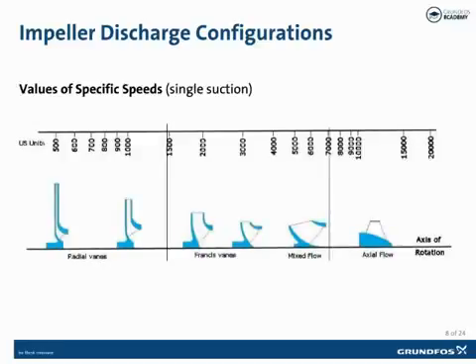Specific speed is a dimensionless value. This chart shows the relationship of specific speed with impeller types. Specific speed is defined as the speed at which a given impeller would operate if reduced proportionally in size so as to deliver a flow of one gallon per minute at one foot of head. An impeller generating a very large volume of water at very low head has a high specific speed, while an impeller generating very low flow at very high head has a low specific speed.